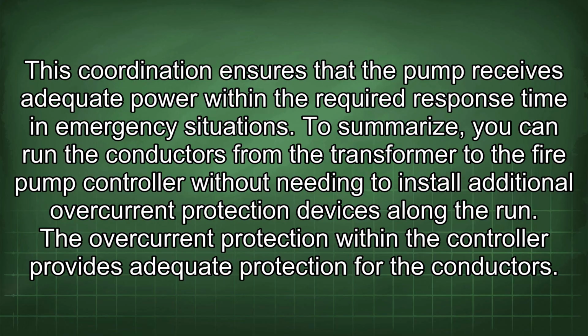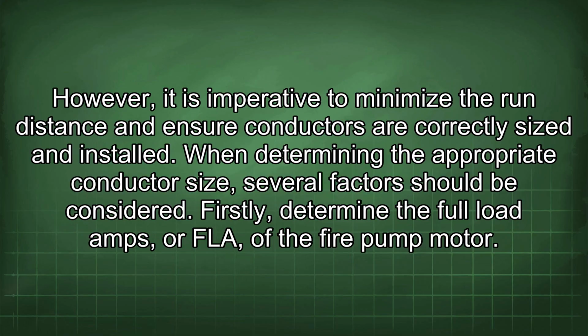To summarize, you can run the conductors from the transformer to the fire pump controller without needing to install additional overcurrent protection devices along the run. The overcurrent protection within the controller provides adequate protection for the conductors. However, it is imperative to minimize the run distance and ensure conductors are correctly sized and installed.